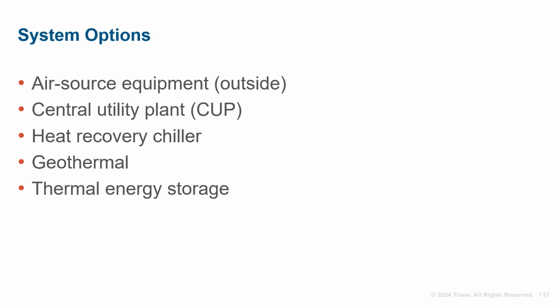In general, we are seeing emergent system types frequently used in electrified systems, not only in retrofit scenarios. I will briefly discuss a few common system types and explain why certain options are selected over others. Sometimes, various systems are combined to maximize efficiency, minimize costs, and utilize available space. In a two-pipe changeover system, where the chillers are located outside, heat pumps are installed to perform double duty. Perhaps for a smaller school that has two-pipe hydronic distribution to local fan coils or unit vents. The system simply changes over based on outdoor air temperature, schedule, or even manually.